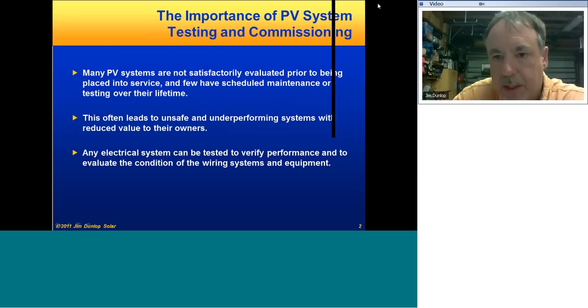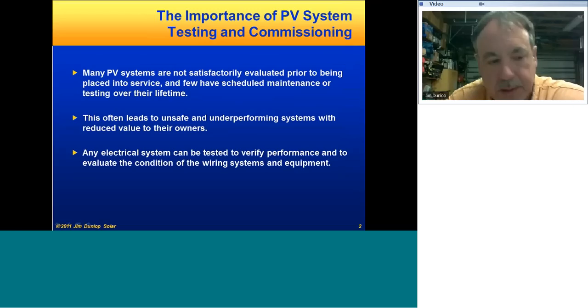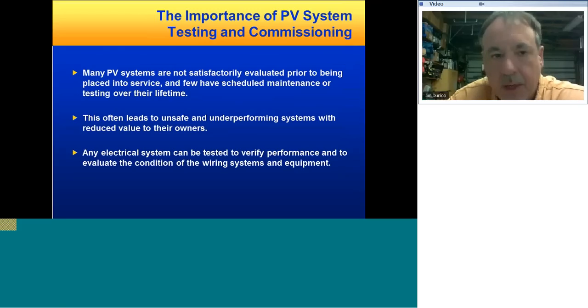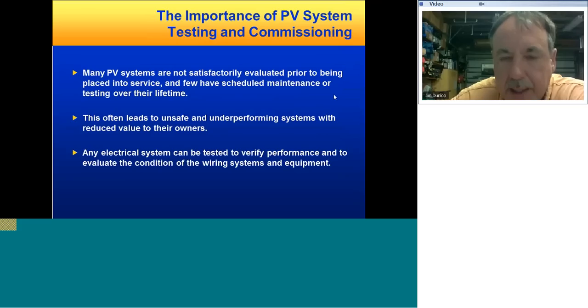Essentially, why is it important that we test and commission systems with an organized approach? Many systems aren't being evaluated satisfactorily right now. Few of them are being maintained or tested over their life. That's going to lead to unsafe, underperforming systems and reduced value to the owners. There are a lot of things that can be simply done. The inverters are going to do a lot of these tests for us ultimately, and some tests are already being done by the inverters, so that's going to make things a little bit easier. But there's still additional testing that can be done, certainly to identify faults in the system when they happen.